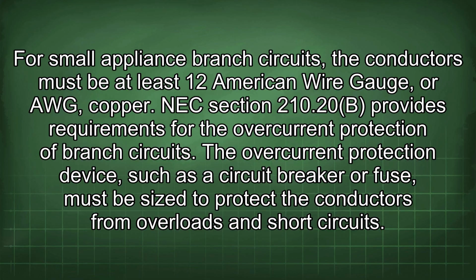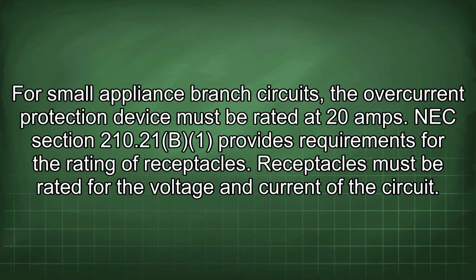NEC section 210.20(B) provides requirements for the overcurrent protection of branch circuits. The overcurrent protection device, such as a circuit breaker or fuse, must be sized to protect the conductors from overloads and short circuits. For small appliance branch circuits, the overcurrent protection device must be rated at 20 amps.